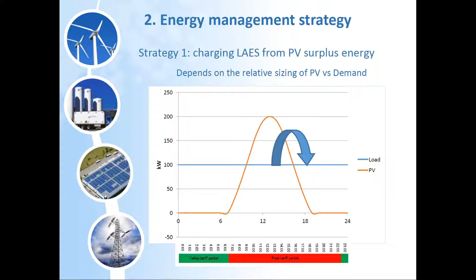Your reference here is which is the peak tariff you're trying to fight against. In this case, the peak tariff should be higher than the use cost of your storage system to have an interesting case. The use cost, being simplistic for this example, is your investment cost divided by the cycle life of the system. So in this case, if we consider a 1 megawatt hour capacity, we would get a reference peak tariff of 40 euro per megawatt hour.